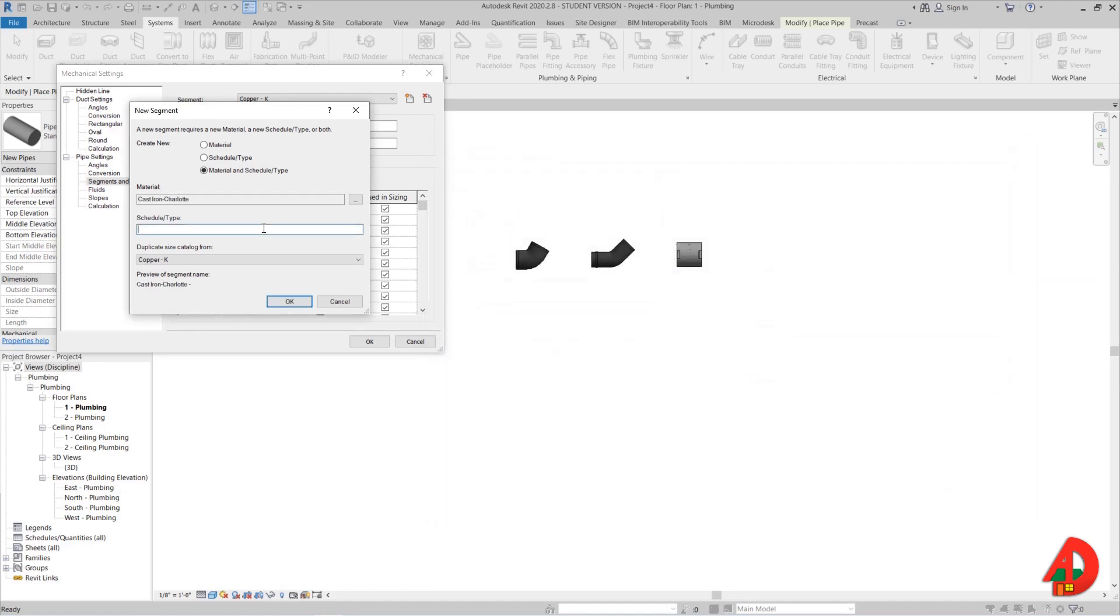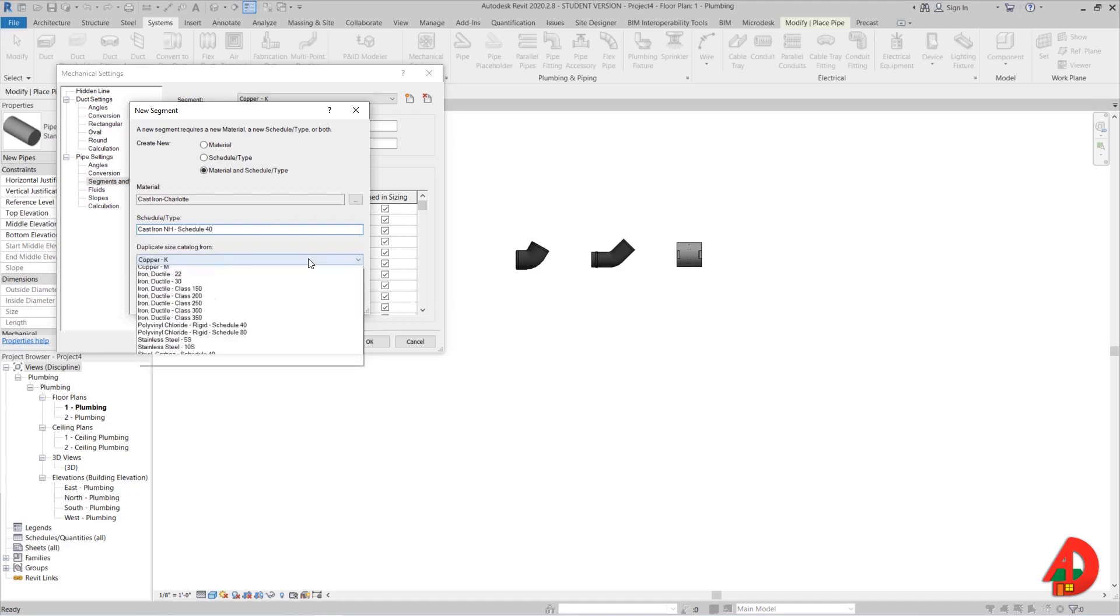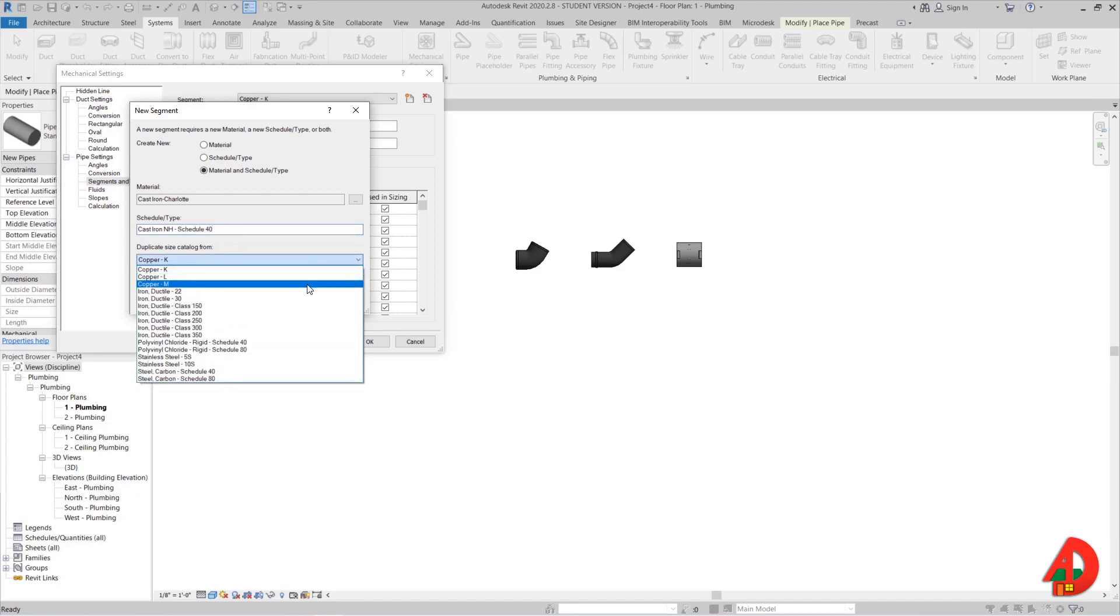I will check material and schedules type, and for material I will look for cast iron Charlotte. The reason we have this material is because I previously imported the cast iron fittings. For the name I will type cast iron NH from no hub schedule 40, and then duplicate size catalog. I will select steel carbon schedule 40.